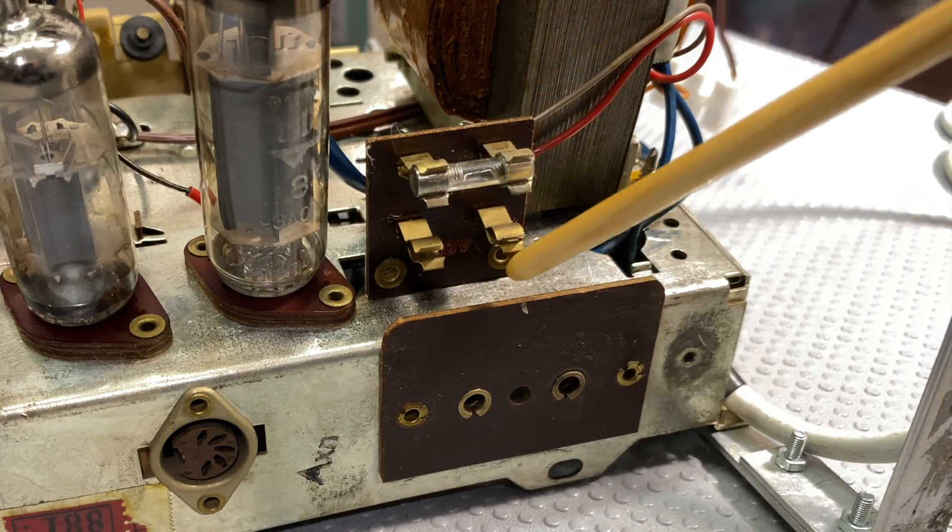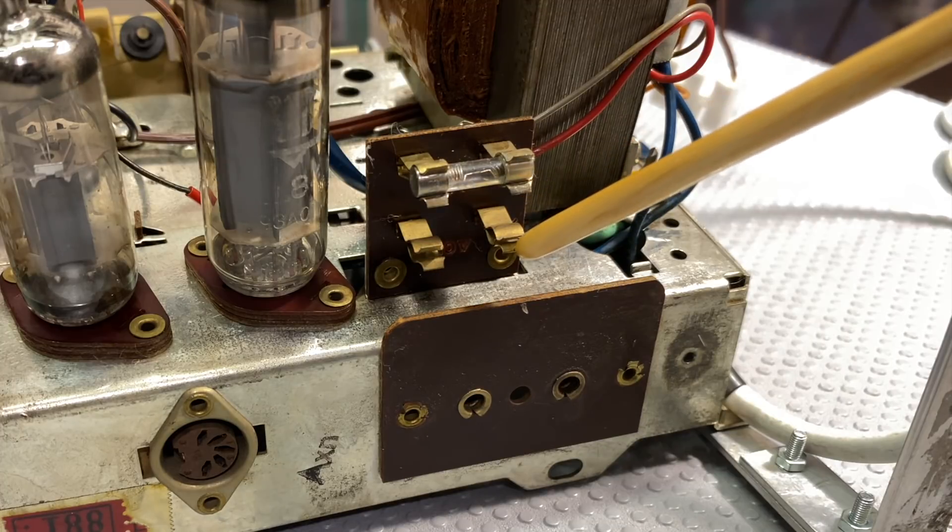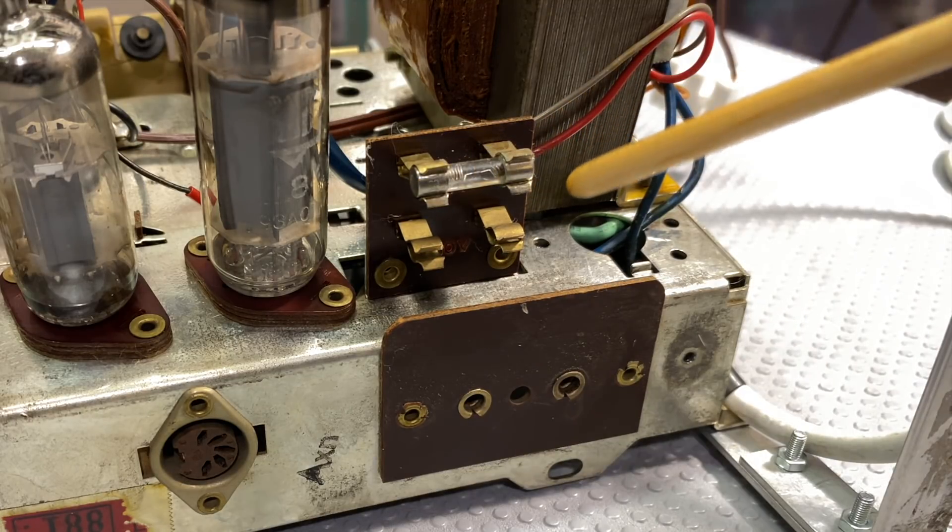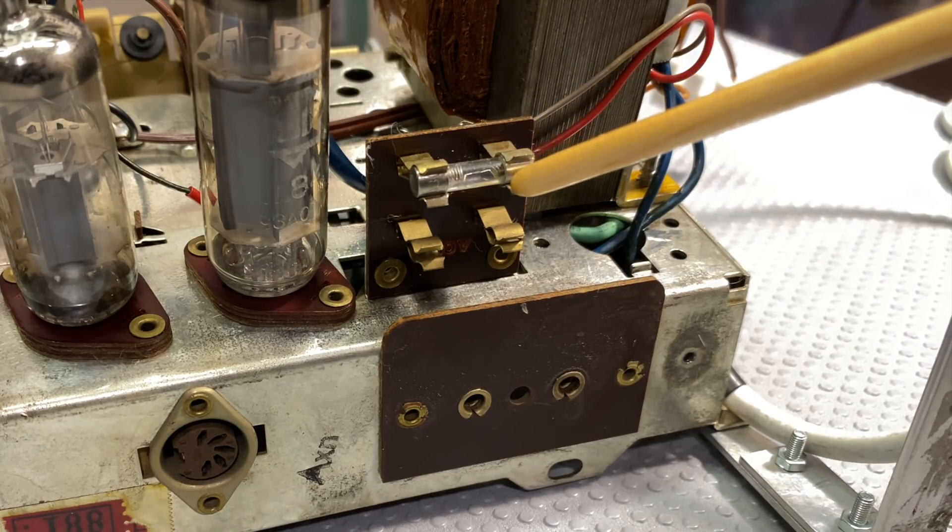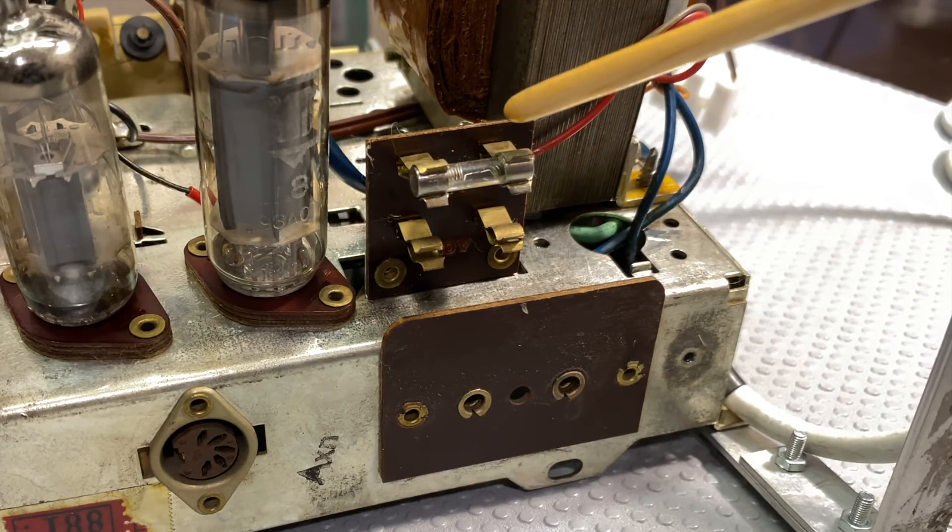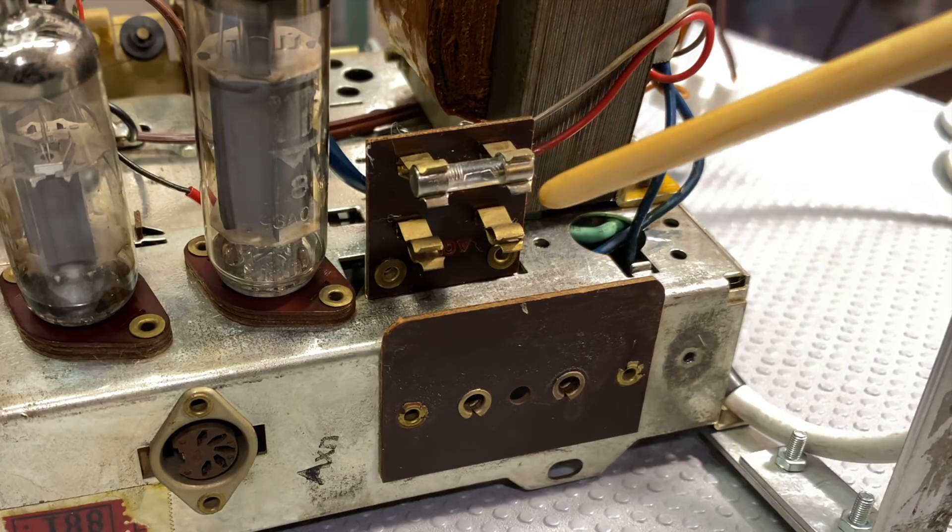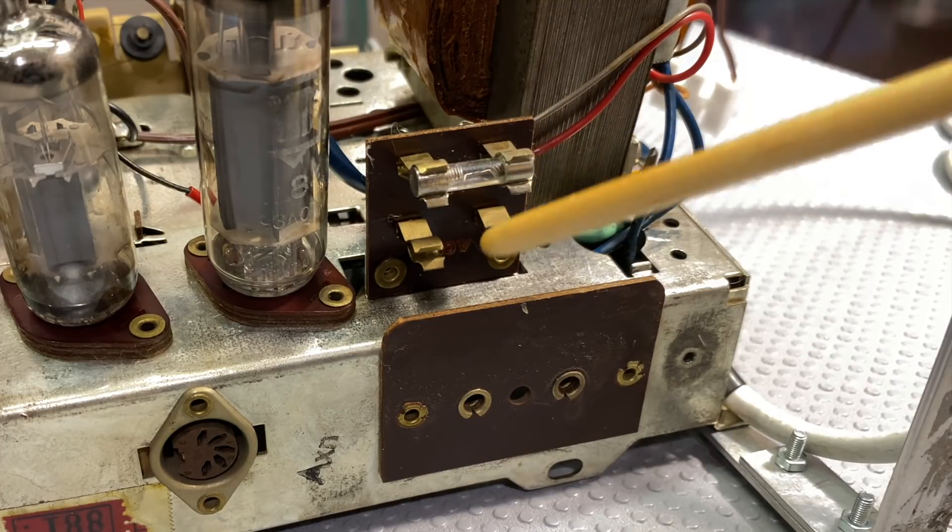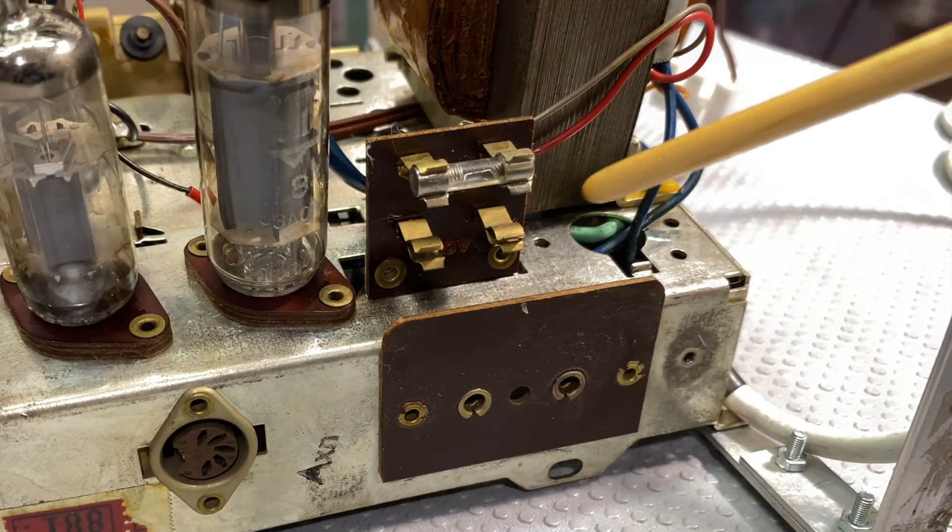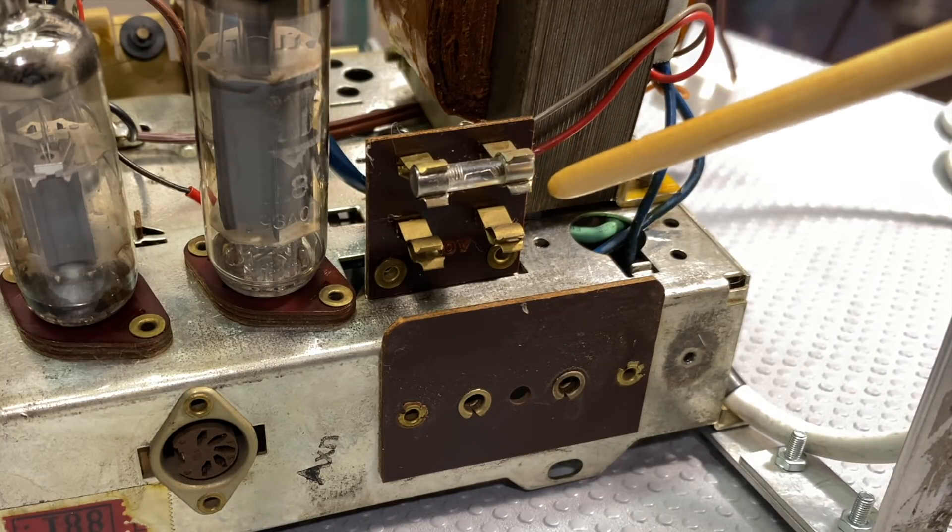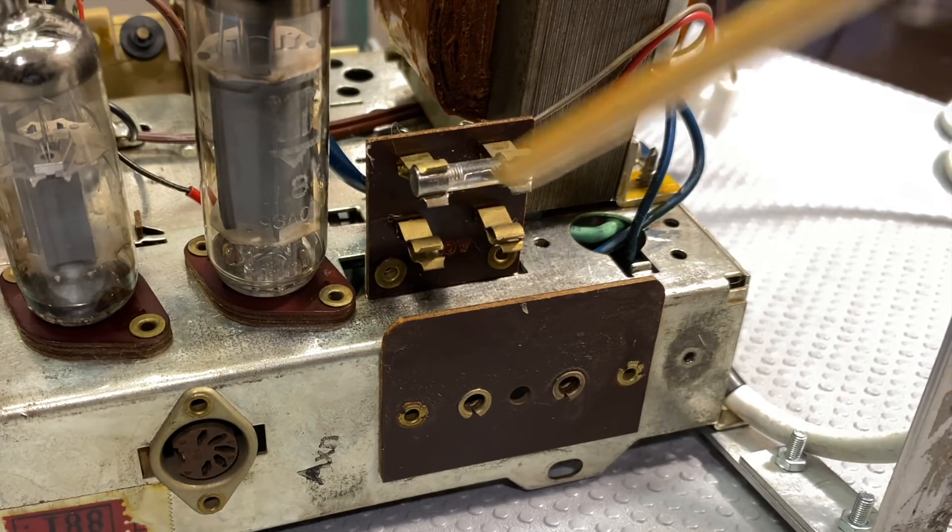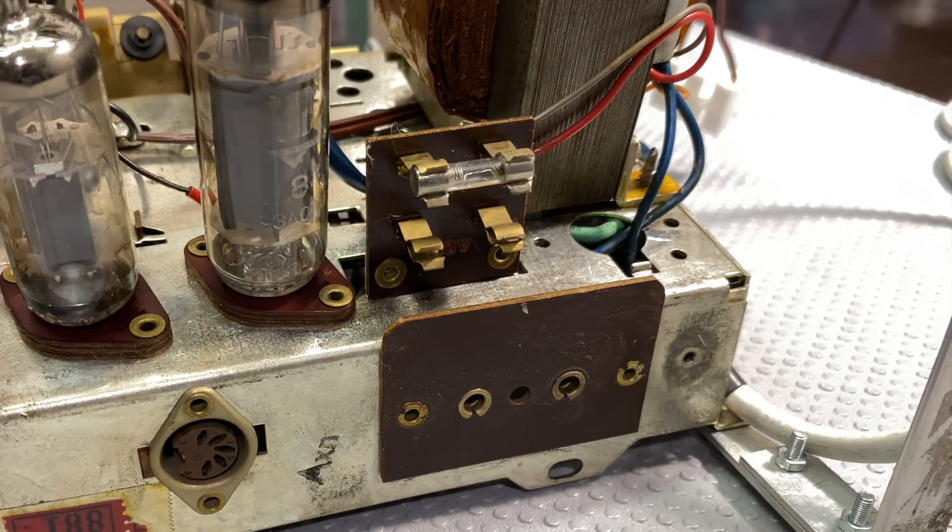It's a 300 milliamp fuse for the 220 volt option. If you go to the bottom here and you choose 110 volts or 115, you need to use a 600 milliamp fuse. So the fuse is fine. But the contacts in this fuse holder were completely tarnished. So when you measure with a multimeter, you're measuring with very low voltages and it's just not enough to break through that tarnish. So what we were not getting was continuity across the fuse or rather from the fuse holder to the fuse connector.